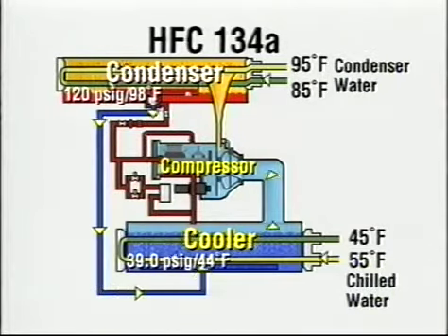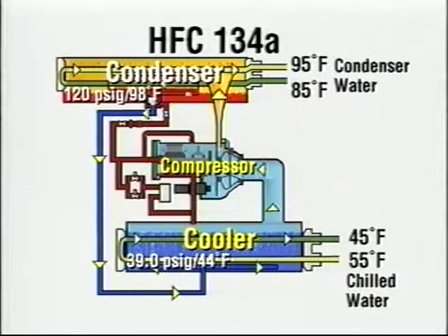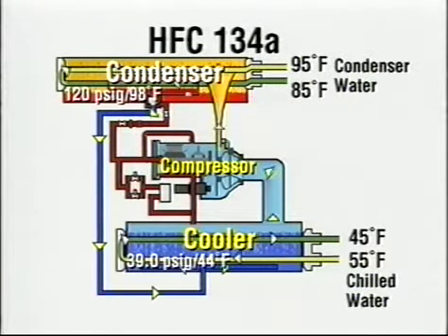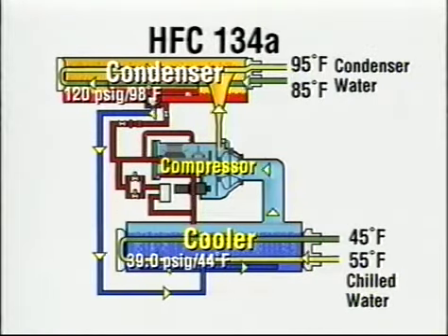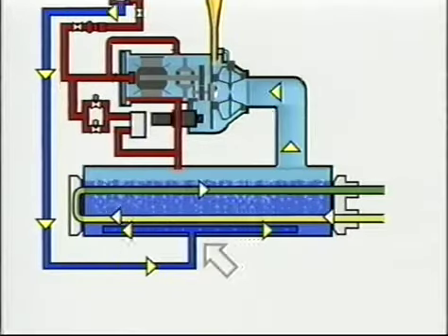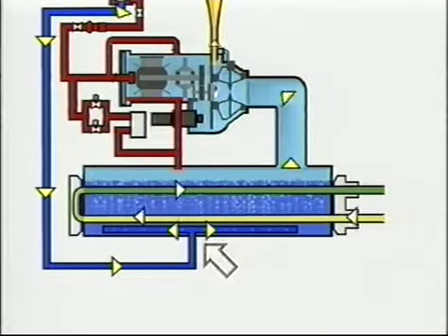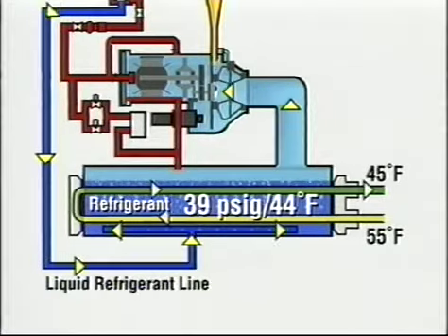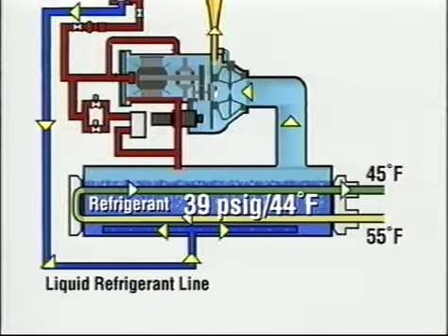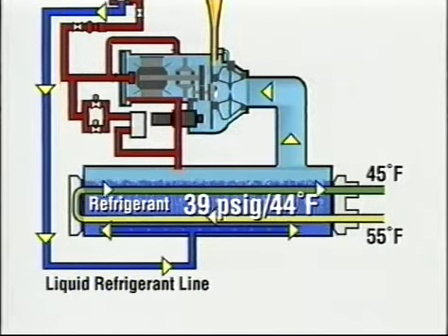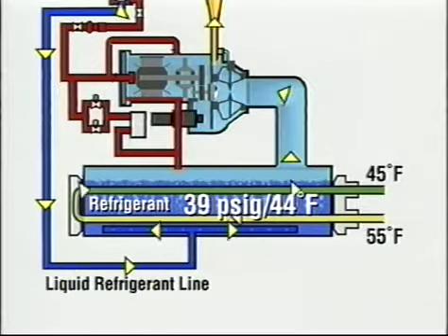Refrigerant pressures and associated saturation temperatures can vary widely based on the type of tubes in the heat exchanger, whether a brine or freshwater solution is used, the pass arrangement on the heat exchanger, and the water flow rate. These values are normally found on the chiller design data specification sheets. The pressures and temperatures shown in this example are typical for a chiller sold today, but variations do exist. We will start where the liquid refrigerant flows into the evaporator. This is a flooded shell and tube heat exchanger with the chilled water in the tubes and the refrigerant liquid in the shell around the tubes. It is called flooded because the liquid refrigerant covers the chilled water tubes.